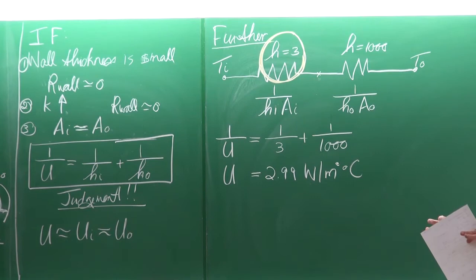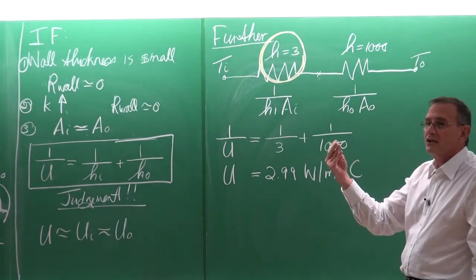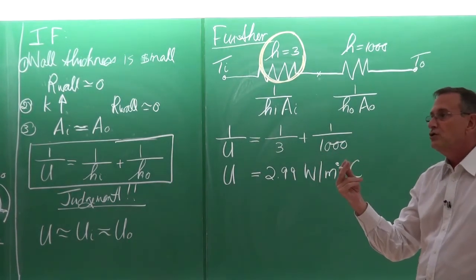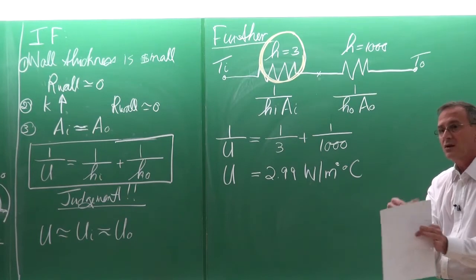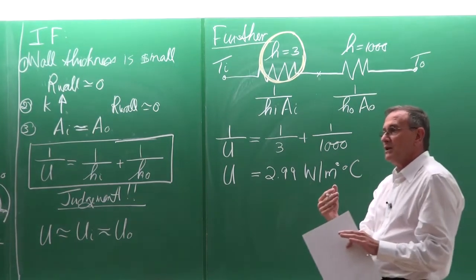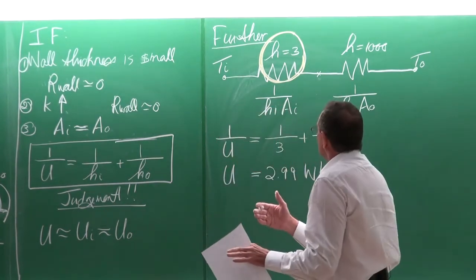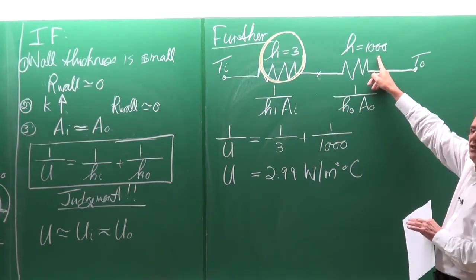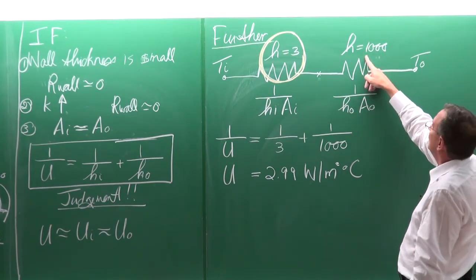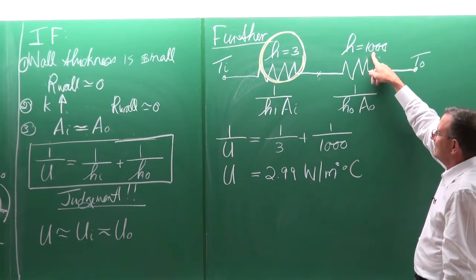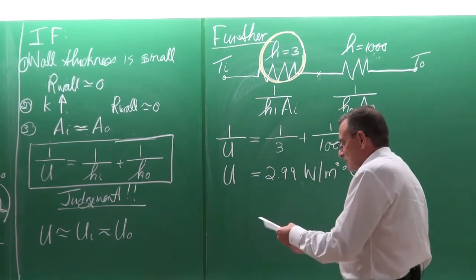If you have a case like this and want to enhance heat transfer, there are two methods: change the surface area, or put on fins — which also increases surface area. If you put fins on the high-h side, you are just wasting money — it will not help. If you increase h_outside to 2000 or even 10,000, the answer is still approximately 3. This is a very important thing to realize.